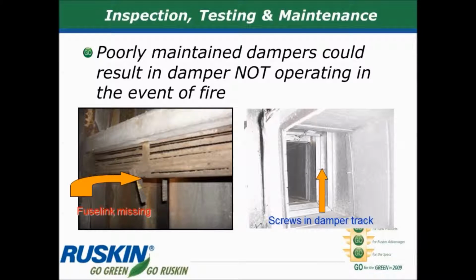Here are a couple of photographs from actual job sites showing older dampers that have not been maintained, have not been tested. And in the photograph on the left, the fusible link is gone. This damper should be closed. However, it's so dirty and gunked up that it's stuck in the open position. And if there ever was a fire here, those blades would not close and flame would be allowed to pass from one side of the rated wall to the other, which is completely in violation of what we're trying to do with these life safety dampers.